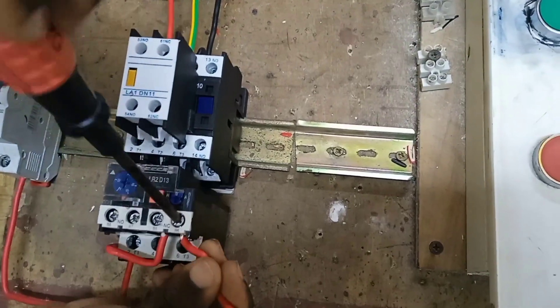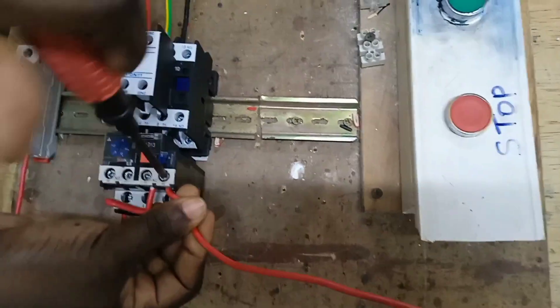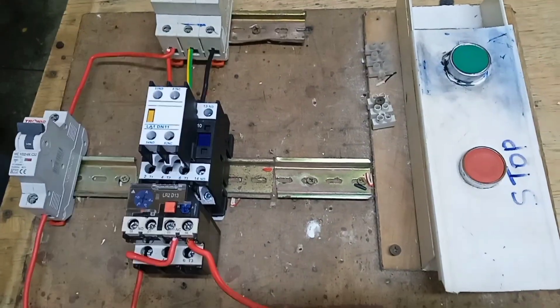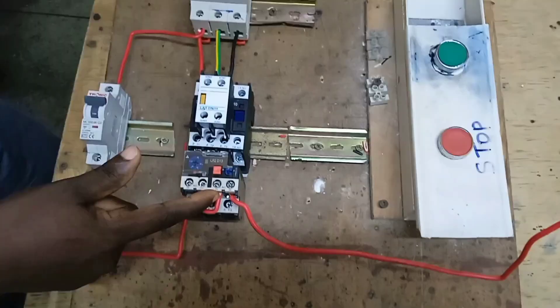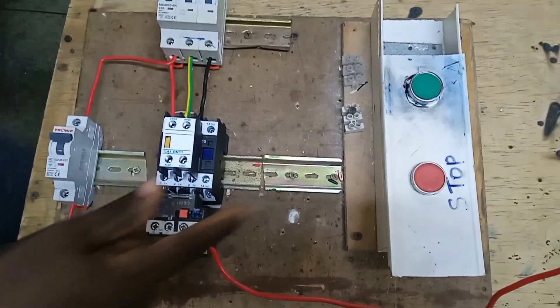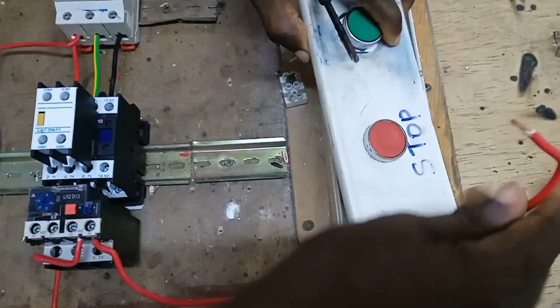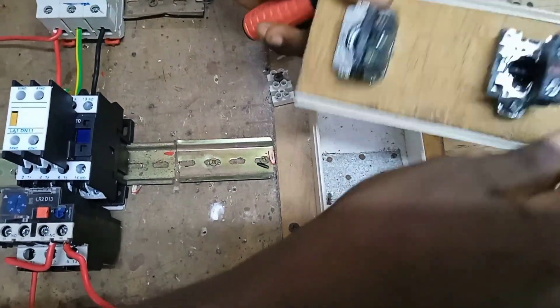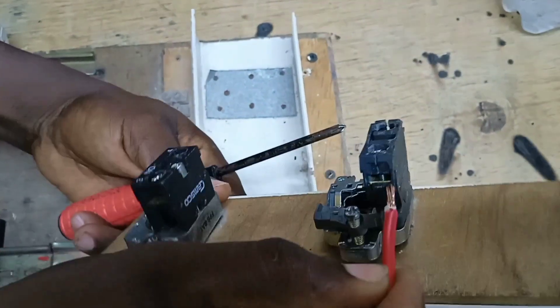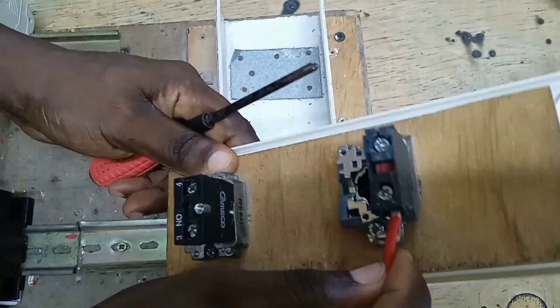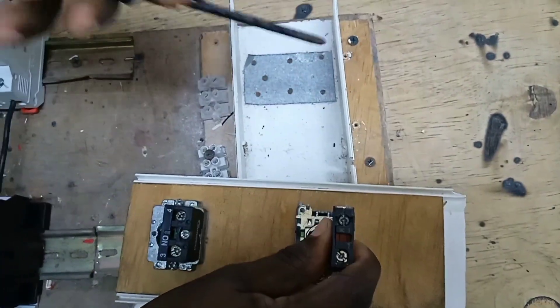We connect this cable to terminal 96 of the overload relay. After connecting the cable to terminal 96 of the overload relay, we connect it to the input of the stop push button, which is a normally closed contact, a normally closed switch. We connect it to the input of the stop push button here.